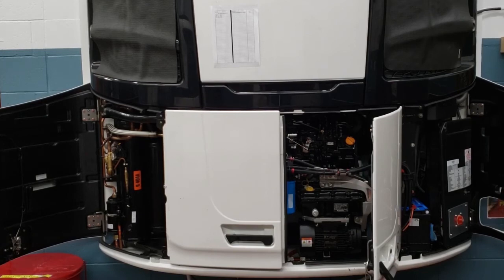If there would have been no refrigerant visible in the sight glass, the unit may have a leak and lost its charge. Either way, if there's no refrigerant to the sight glass, a 608 mechanic is going to have to take a look at it. Thank you very much.